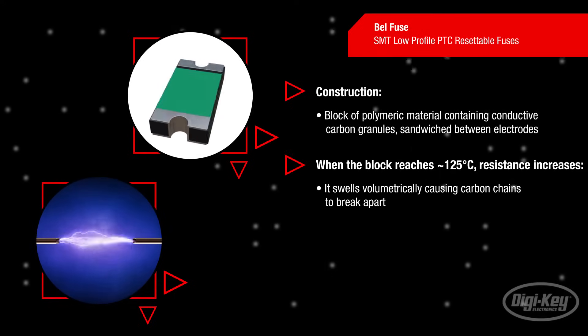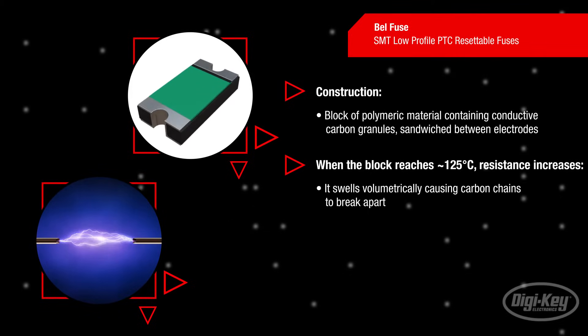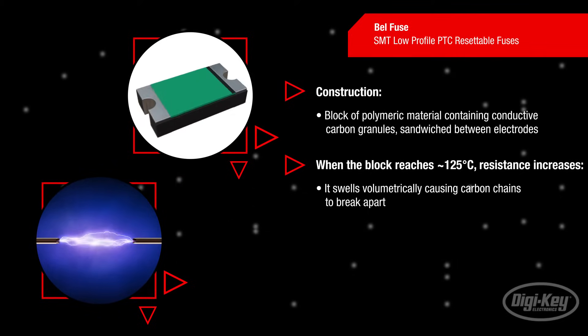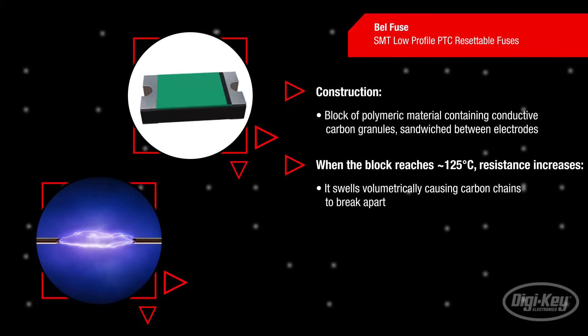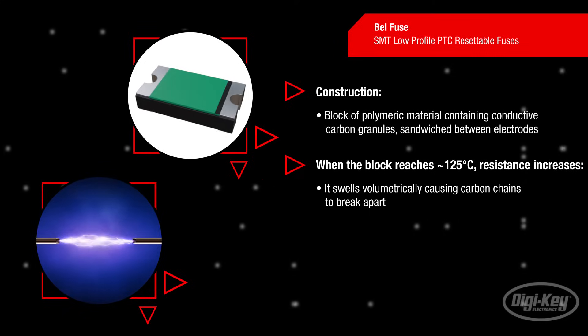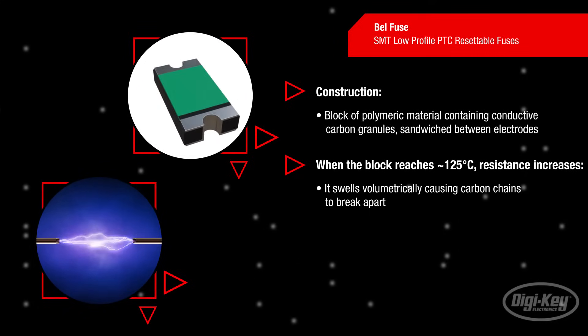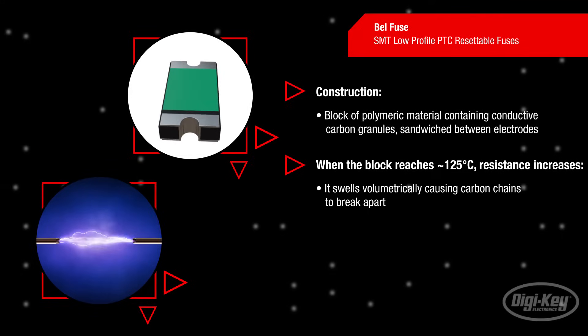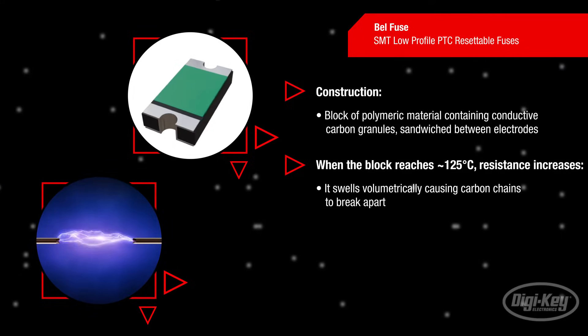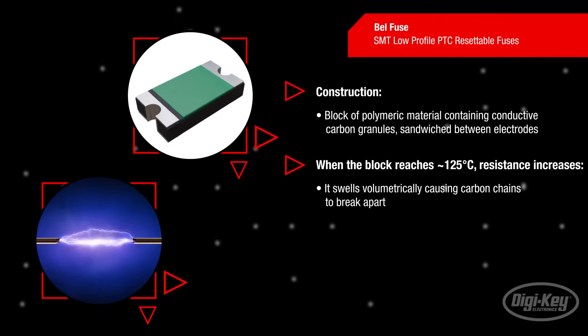When this polymer block reaches approximately 125 degrees Celsius, either due to current passing through it via conductive chains of carbon particles or due to an external heat source, it swells volumetrically. This expansion breaks apart a majority of the chains of carbon granules that run between the two conductive plates.